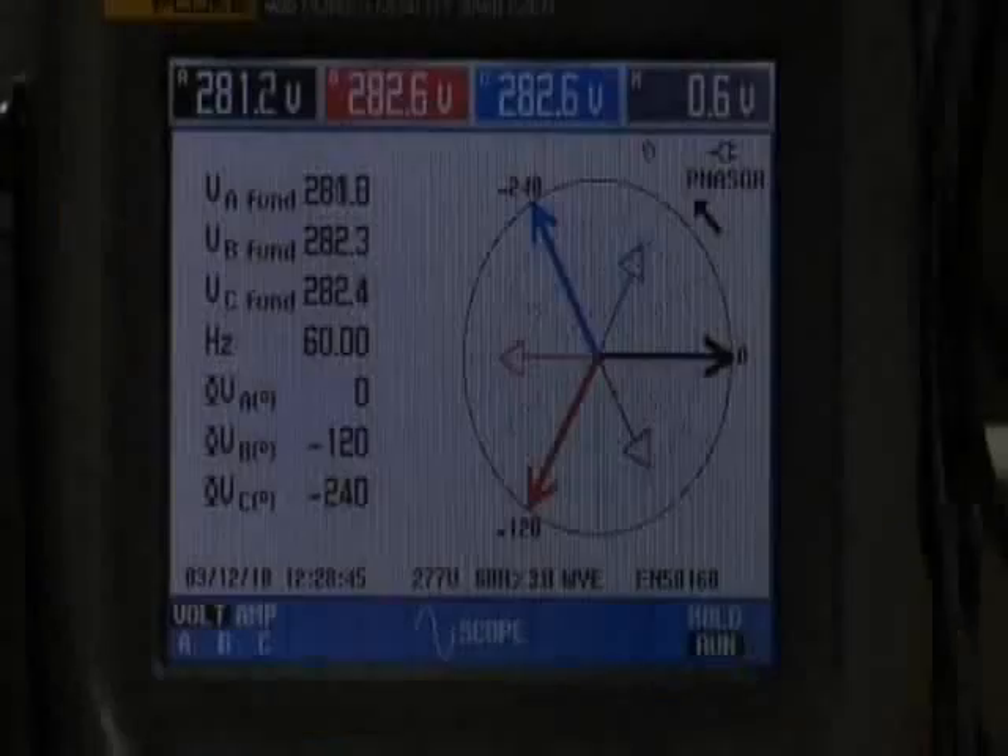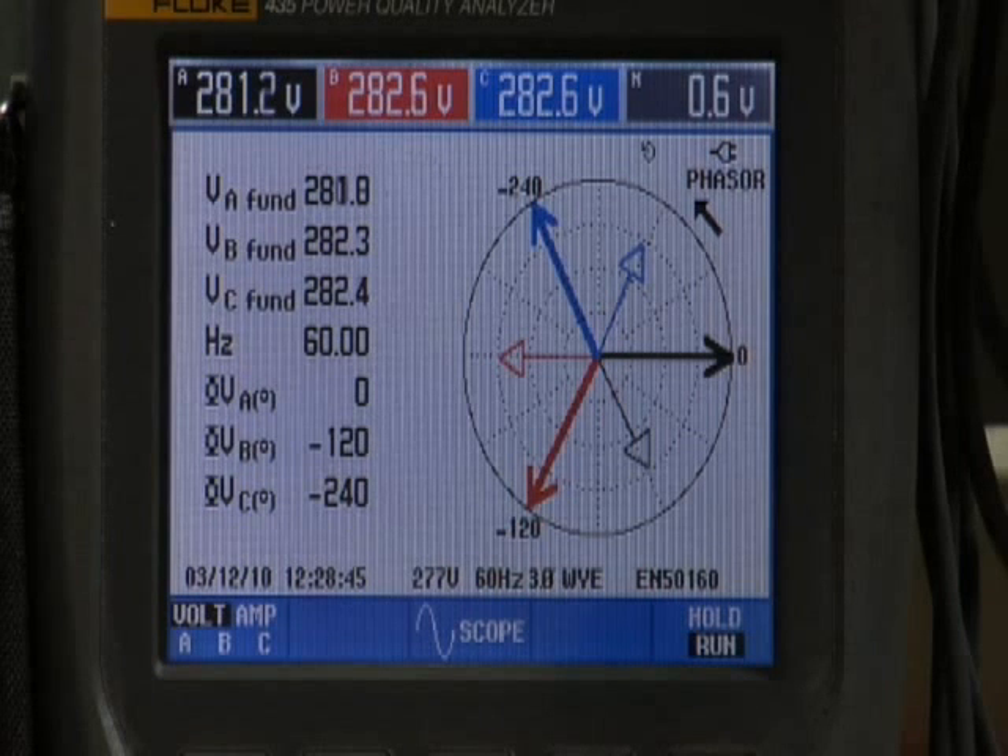Incorrect phase rotation. For normal phase A, B, C rotation, on the phasor diagram, the arrow points in a clockwise direction. At the zero reference point, the thick black line indicates the phase A voltage. Phase A current, the thin black line, can be seen lagging behind the phase A voltage. Phase B voltage is the thick red line at the 120-degree point. The phase B current is the thin red line, lagging behind phase B voltage. Phase C voltage is the thick blue line at the 240-degree point. Phase C current is the thin blue line, lagging behind phase C voltage.